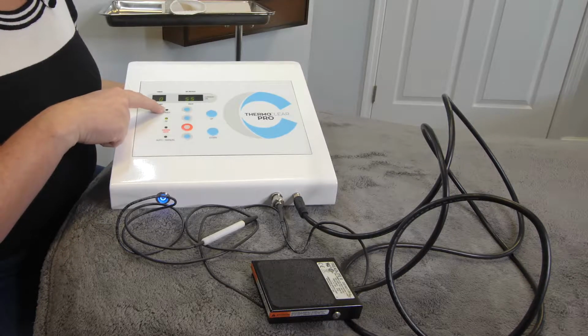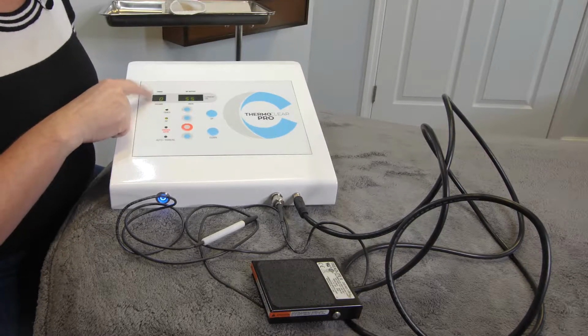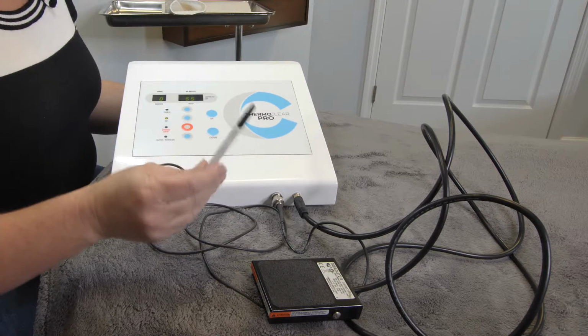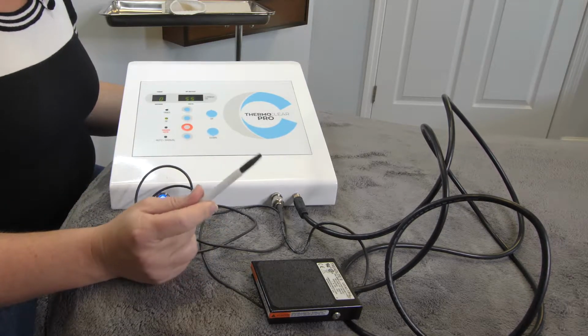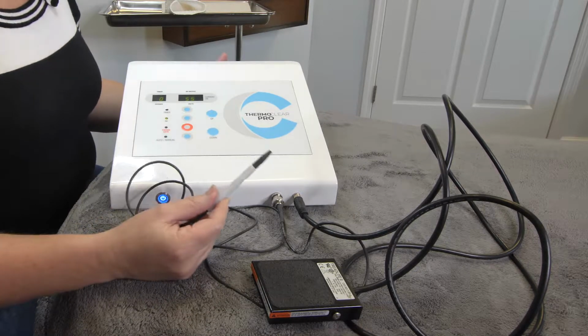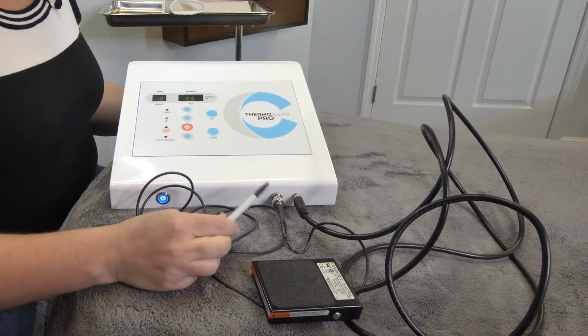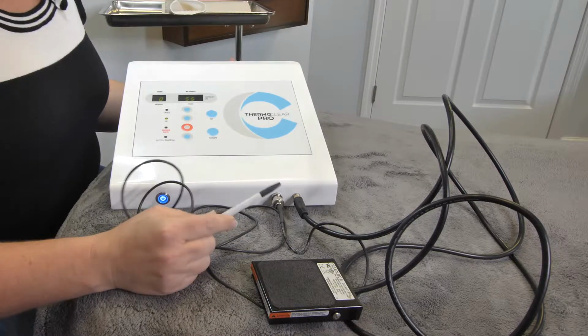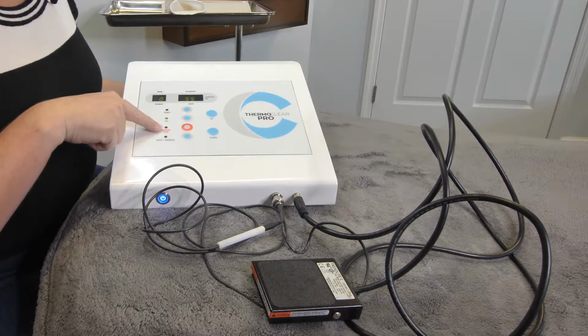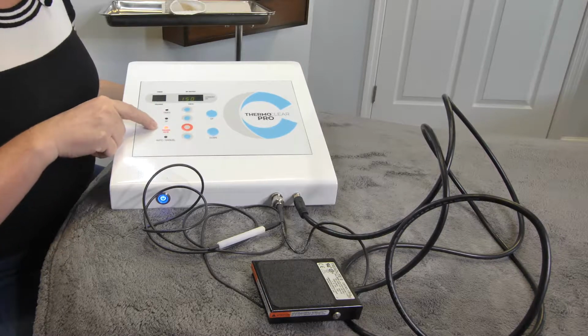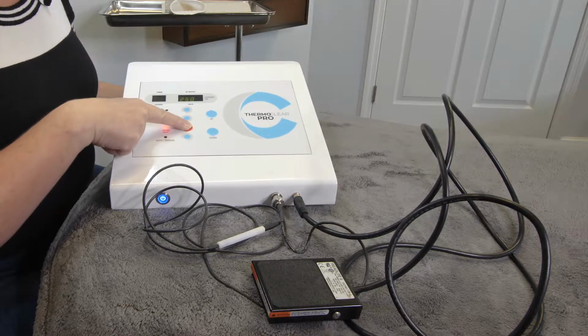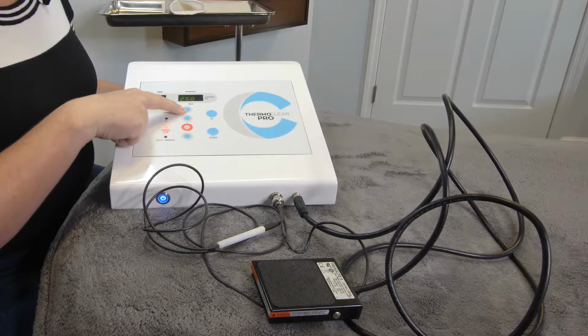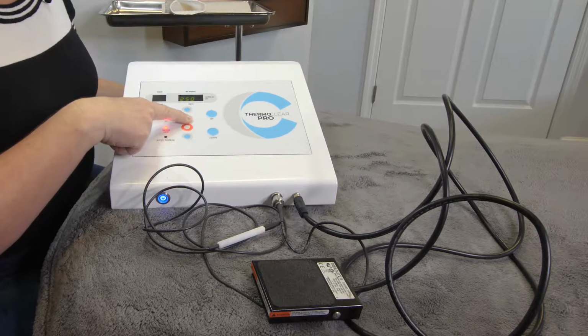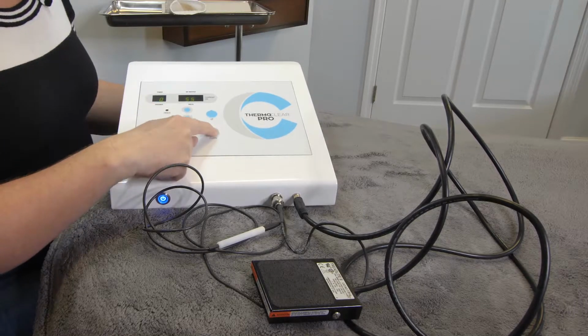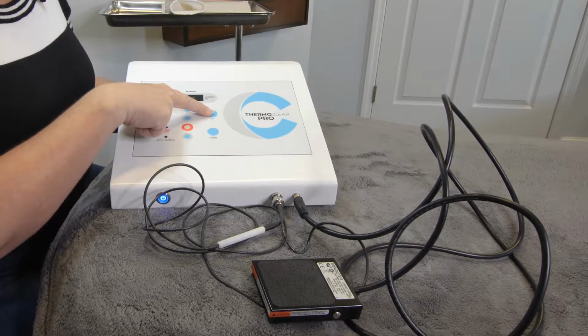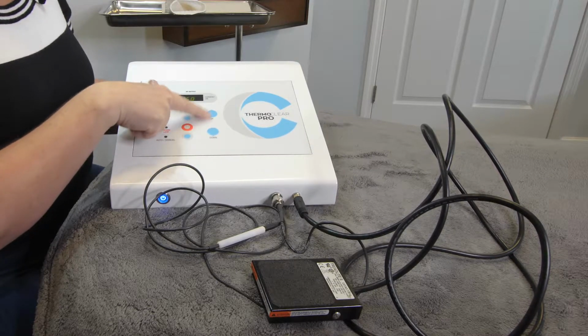In addition, there's a timer that will tell you how long you have to utilize this once you start providing treatment, and it will back off and stop the current flow. That is also designed as a safety feature. And then you have an option for high frequency and low frequency. This would be a high frequency treatment setting, and then low frequency would start out at 40, and then you would work your way up with these indicators here.